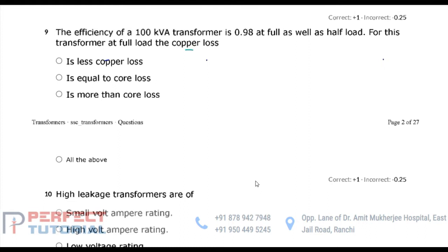देखिए यहाँ पर यूनिट एफिशिएंसी दिया हुआ 0.98 एंड एफिशिएंसी सेम है फुल लोड पर भी एज वेल एज हाफ लोड पर। आप जानते हैं एफिशिएंसी कर्व is a double valued function. Same efficiency can be obtained at different two loadings. Okay, so per unit system के लिए आप efficiency का expression लिख सकते हैं. eta is equal to 1 by 1 plus PCU plus PI. Here PCU is the full load copper loss, PI is the iron loss. One is your kVA rating in per unit system और power factor consider किए है unity, loading है full load. So simply it would be output power in per unit system can be 1 only. So 1 by 1 plus PCU plus PI. This is your efficiency expression in per unit system at full load.